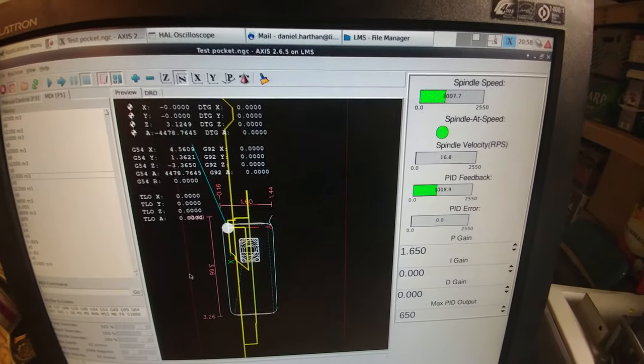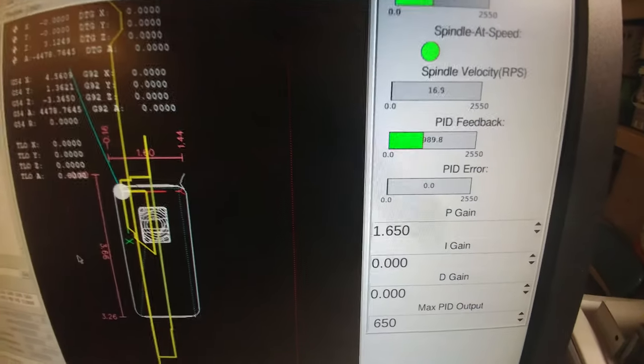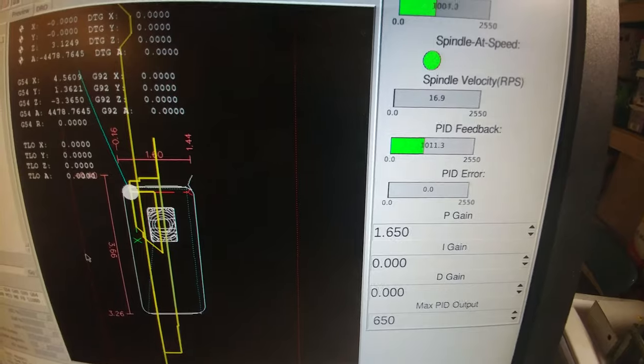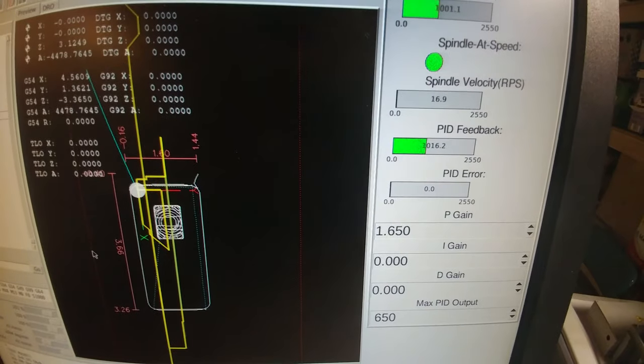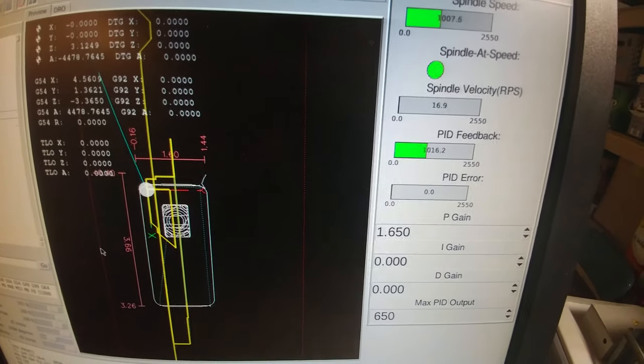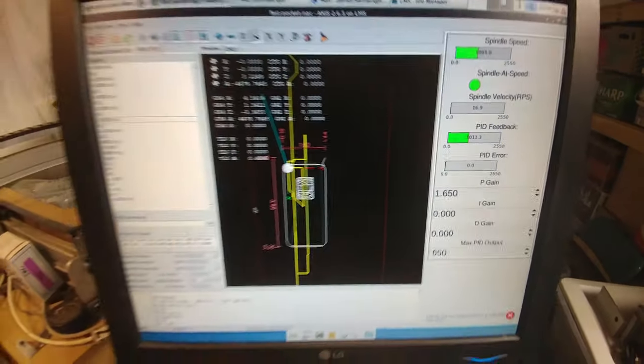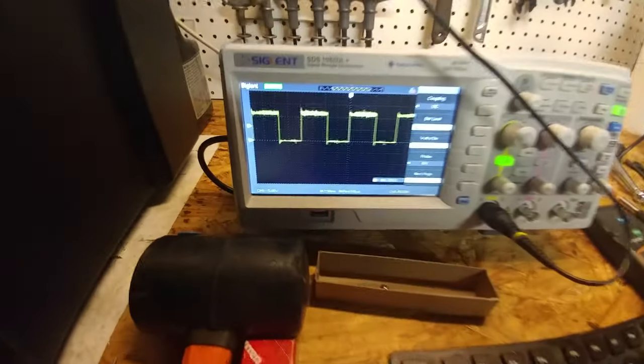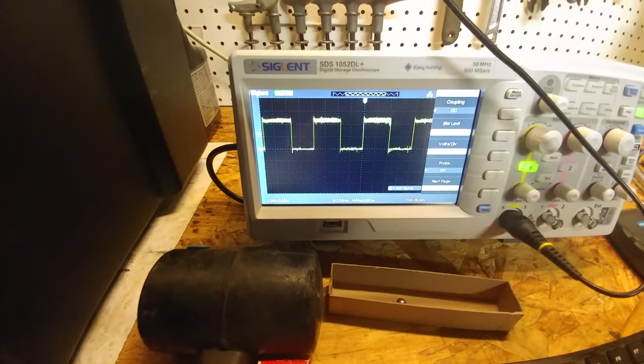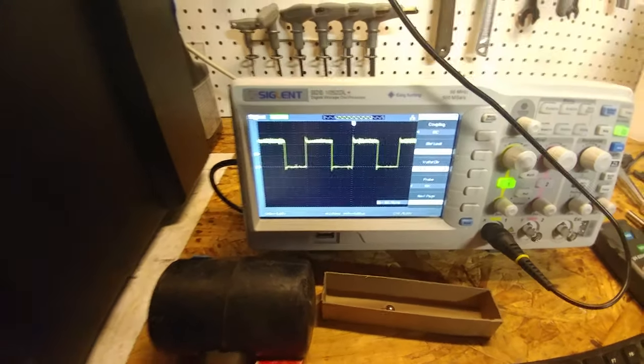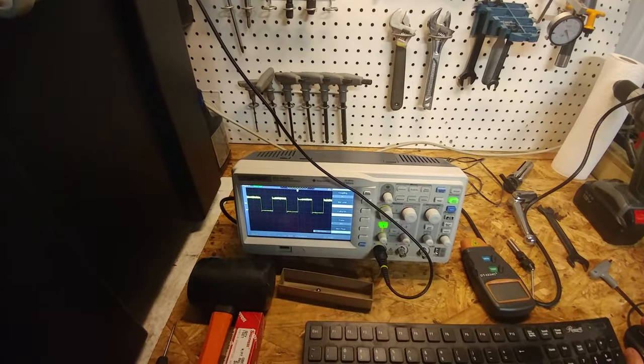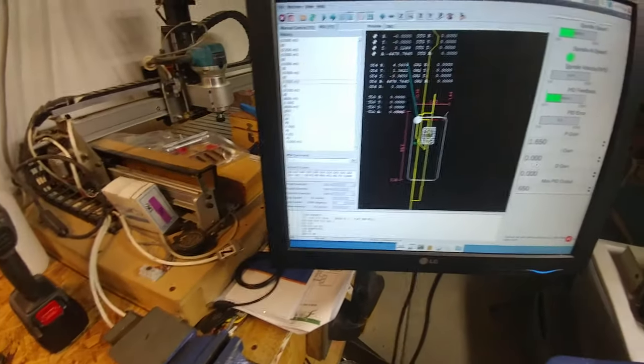Looking at our impulses, they all look good. My encoder is working well and it looks pretty stable, not a lot of variance. The first step of the Ziegler method is to start raising proportional gain until you see instability.